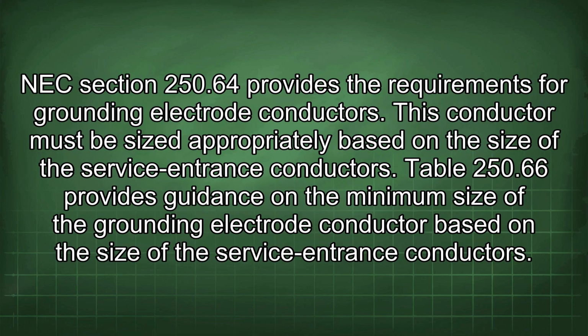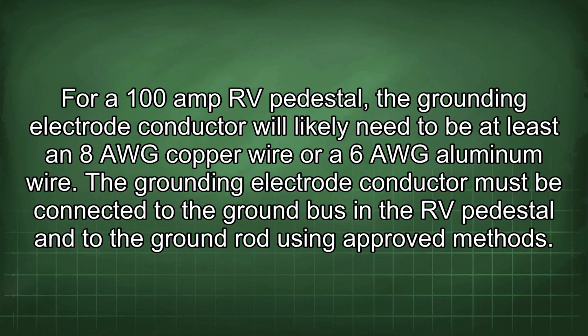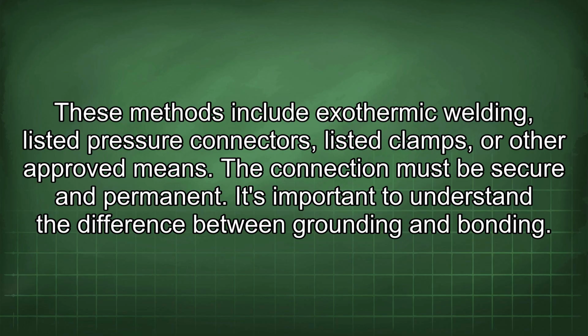NEC Section 250.64 provides the requirements for grounding electrode conductors. This conductor must be sized appropriately based on the size of the service entrance conductors. Table 250.66 provides guidance on the minimum size of the grounding electrode conductor based on the size of the service entrance conductors. For a 100 amp RV pedestal, the grounding electrode conductor will likely need to be at least an 8 AWG copper wire or a 6 AWG aluminum wire. The grounding electrode conductor must be connected to the ground bus in the RV pedestal and to the ground rod using approved methods. These methods include exothermic welding, listed pressure connectors, listed clamps, or other approved means. The connection must be secure and permanent.